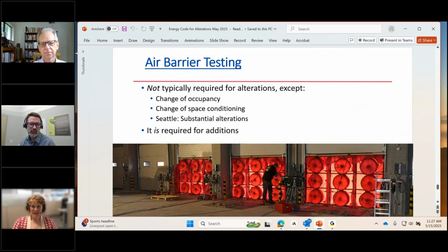Gia wanted to clarify: if the old equipment was above the threshold, but the new system based on actual load calcs is below the threshold, can you avoid the commissioning step? If you're below the threshold in your project capacity, not just that piece of equipment, you do not have to commission regardless of what the old equipment was. It's the new equipment that's triggering it. Thanks, Gia, she heard that and got it.